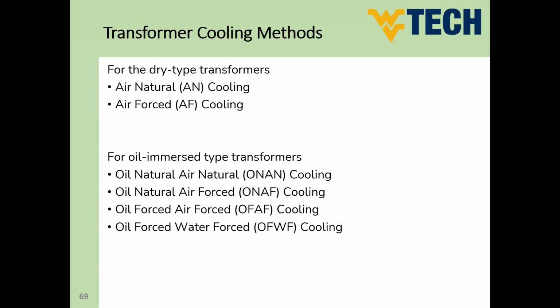Okay. So how can we have the dry type transformer? We have two technologies. One is called AN cooling, which is air natural cooling. The other type is called AF, which is air forced cooling. Air natural means we don't have a source of forced air inside the transformer. But air forced means you have something to force the air to cool the windings, like fans, for instance.